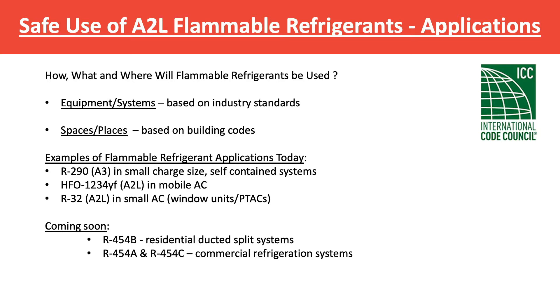The applications of A2Ls really depend on the equipment, the systems, and the spaces where we're going to see A2Ls — and where we have already seen some adoption. That's the how, what, and where they'll be showing up, all based on risk analysis, safety standards, and building codes. We've had class three flammables like propane and butane in small charge self-contained systems for a while, and we're starting to see A2Ls in things like automotive and some small packaged AC units.